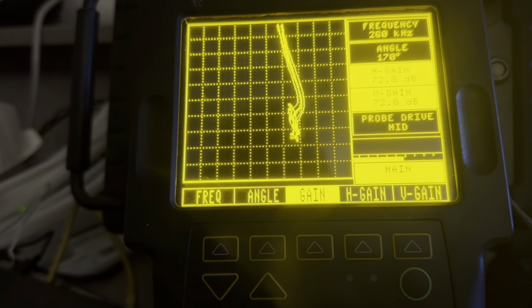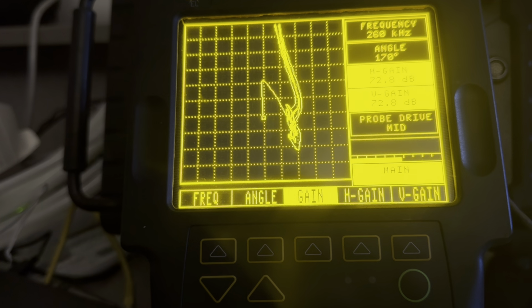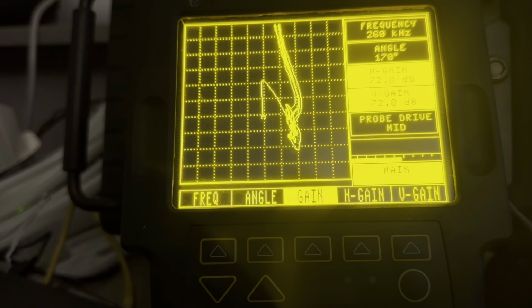With the Nortec 1000. All right, so far we did some surface scanning with a pencil probe on non-ferrous material, aluminum. Then we just did a weld inspection with a differential plus point probe. Now, one word about the plus point probe. That particular flaw that was vectoring in the positive direction was an axial notch. Now, if I were to keep my probe rotation in the same orientation and scan past a circumferential notch, it would be vectored in a negative direction.